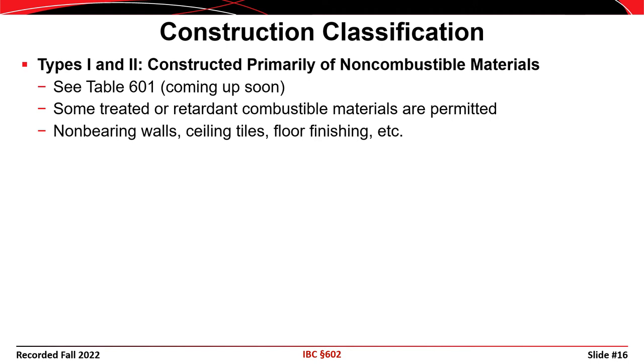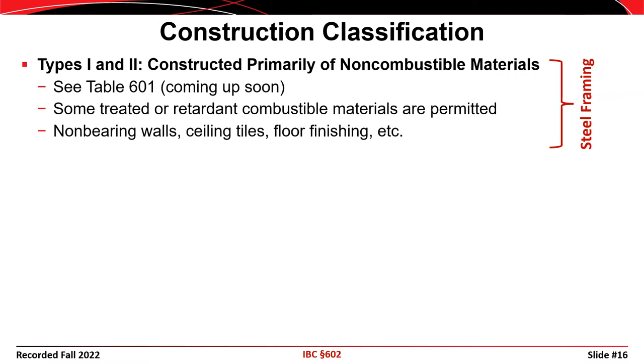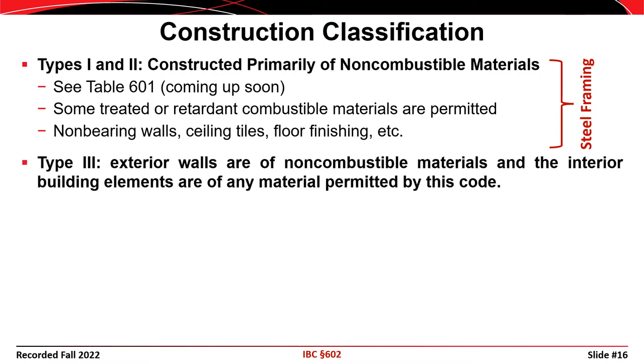Construction Types 1 and 2 are basically constructed of non-combustible materials, with the exception of some treated or fire retardant materials used in non-structural applications. Steel frame structures are generally either Type 1 or Type 2. Type 1 is sometimes referred to as fire-resistant construction and Type 2 is sometimes referred to as non-combustible construction. Type 3 construction is characterized by buildings with exterior walls made of non-combustible materials while the remaining portions of the structure are made up of any material permitted by the code.